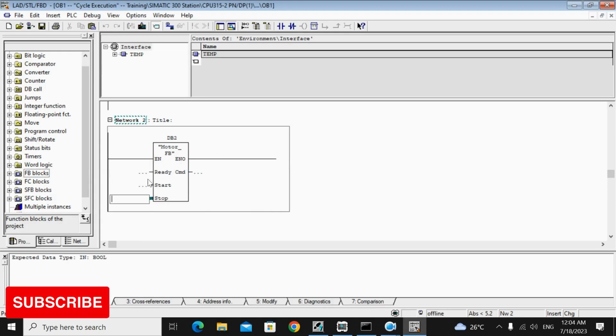Suppose you make a function block with 20 inputs for one motor, but in another motor maybe one input is not present. For a function you have to put a dummy address or dummy tag, but for an FB you can leave it as it is. No dummy tag or dummy variable is required for an FB.